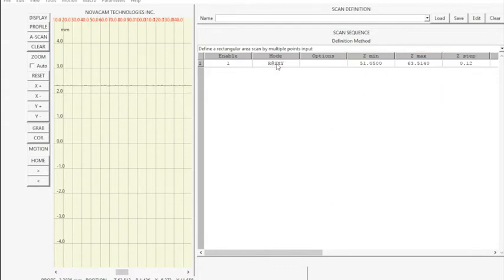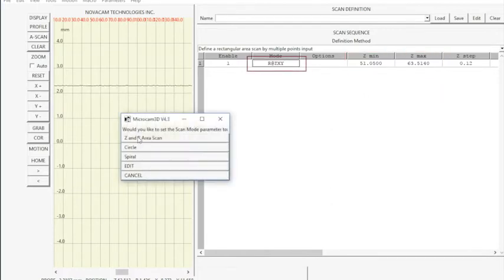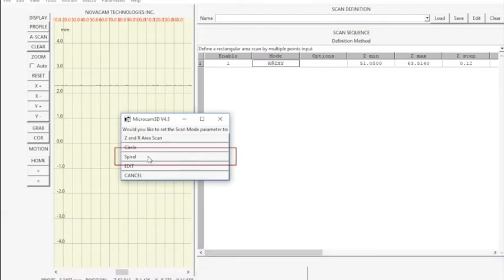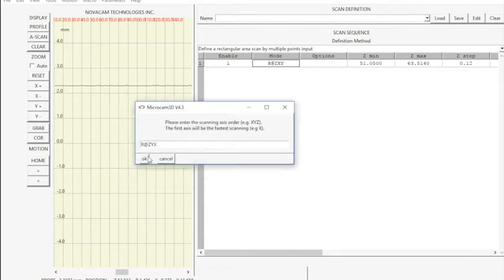On the mode field, we have the options of scanning the hole in different motion patterns. We will pick the spiral pattern, which is the most efficient one because as it goes into the bore, it simultaneously rotates and thereby produces a spiral point cloud. At the same time, the software prompts us also for the speed at which it will rotate, which we will accept, the value that is proposed by the software.